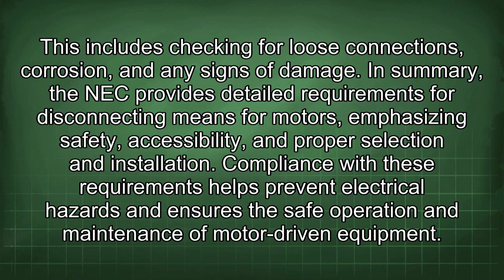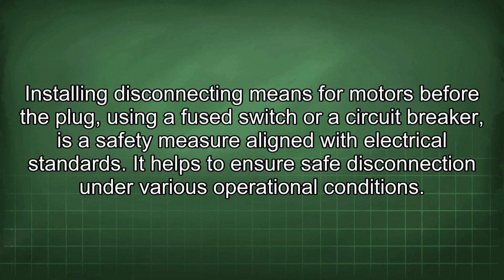In summary, the NEC provides detailed requirements for disconnecting means for motors, emphasizing safety, accessibility, and proper selection and installation. Compliance with these requirements helps prevent electrical hazards and ensures the safe operation and maintenance of motor-driven equipment. Installing disconnecting means for motors before the plug, using a fused switch or a circuit breaker, is a safety measure aligned with electrical standards. It helps to ensure safe disconnection under various operational conditions.